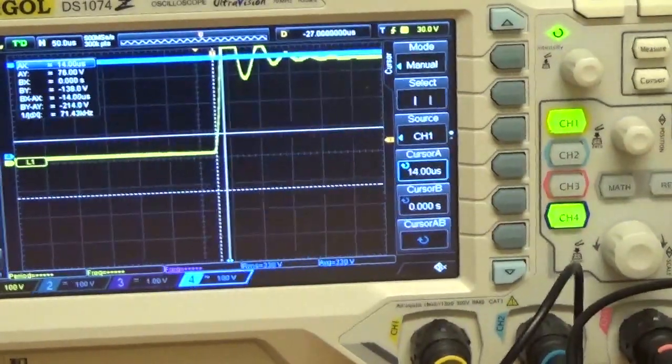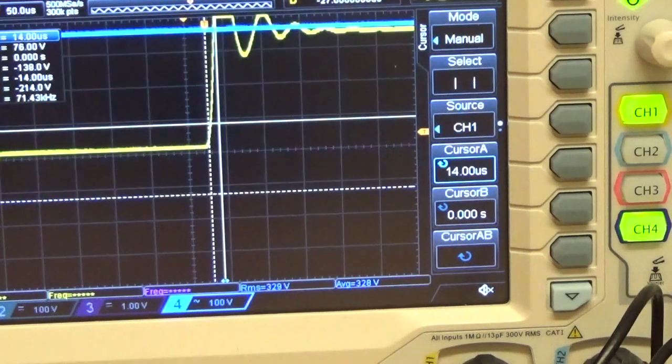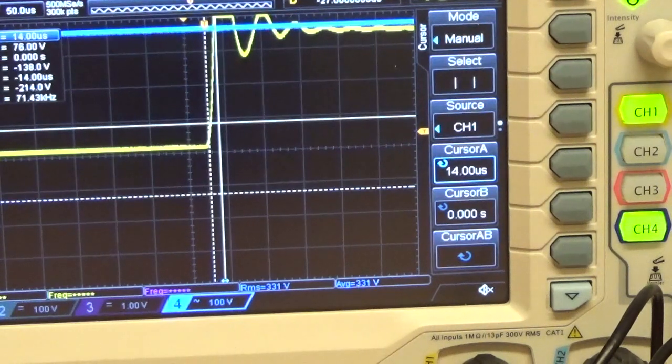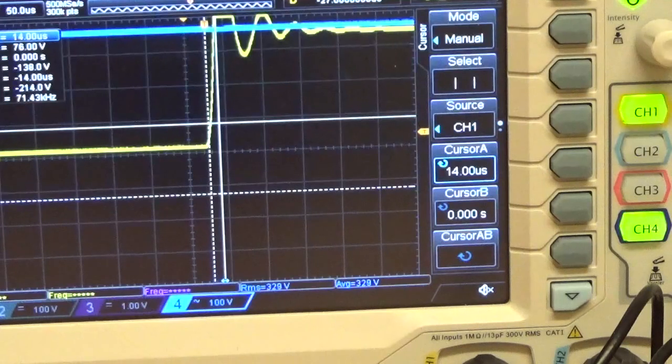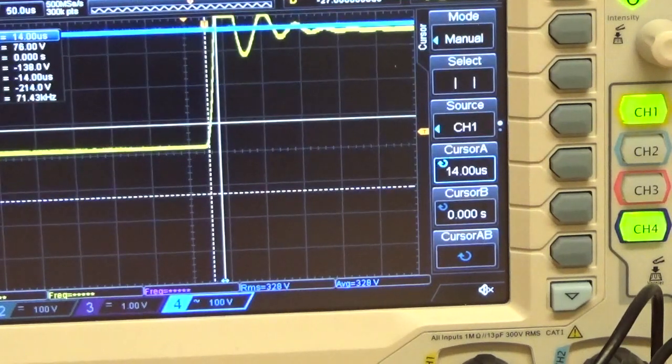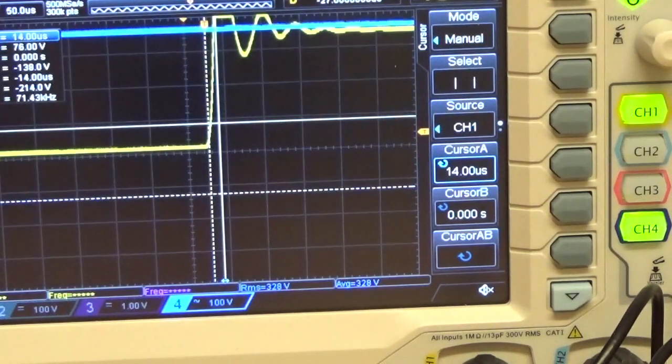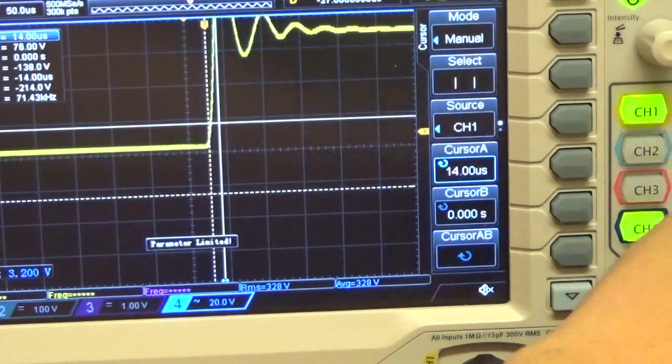And this is the point now I'm going to talk about that big inductor that's on the front of it. Because it's switching at such a high rate and fast, snapping on that quick, it can actually cause harmonics in the mains and RF as well. The inductor is basically used for RF suppression and any nasty little glitches that you might get in the mains. It's because of this switching that the inductor's placed in the dimmer circuit.